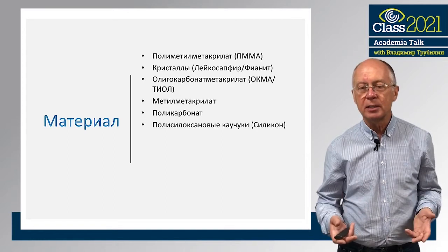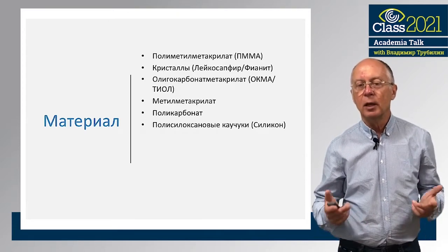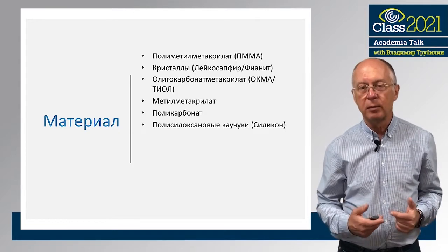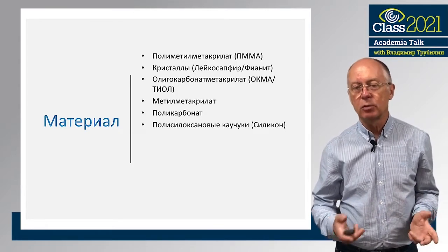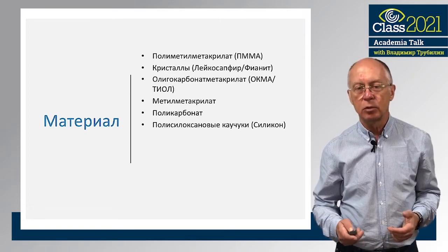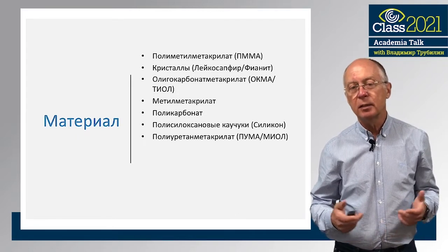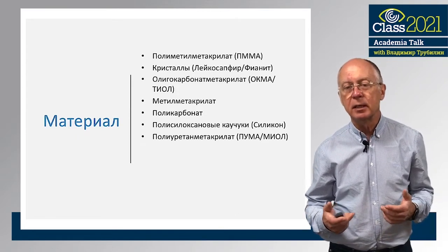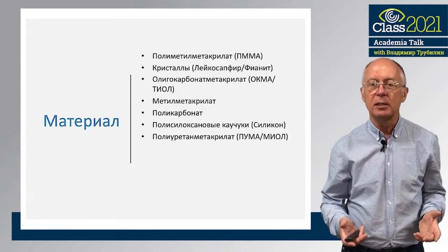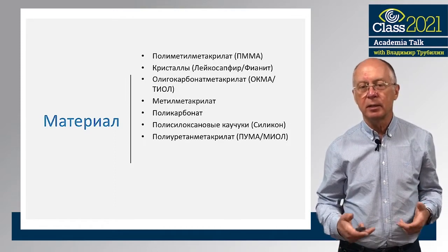Combining liquid silicon with silicon IOLs is impossible, since liquid silicon is absorbed onto the surface of the lens, entirely damaging optical properties of the lens, and it is almost impossible to remove it from the surface of the intraocular lens. So the research into this field opted for developing lenses from a variety of soft materials, and in particular from polyurethane methacrylate.